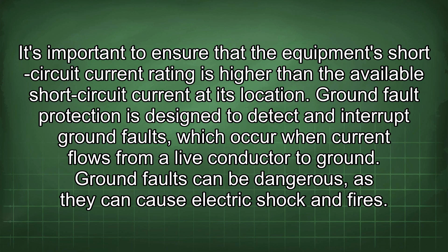Ground fault protection is designed to detect and interrupt ground faults, which occur when current flows from a live conductor to ground. Ground faults can be dangerous, as they can cause electric shock and fires. Ground fault protection is typically required for services and feeders rated 1000 amps or more. It's important to test ground fault protection systems regularly to ensure that they are functioning properly.